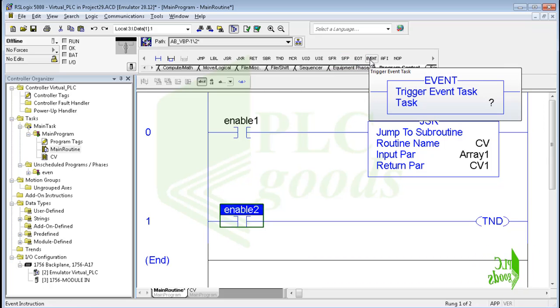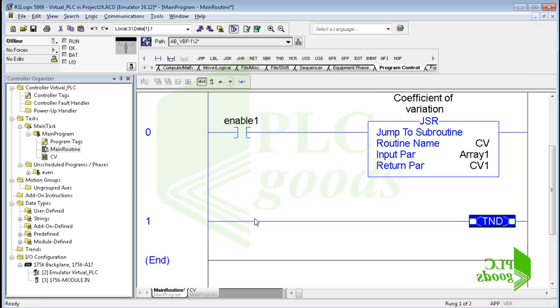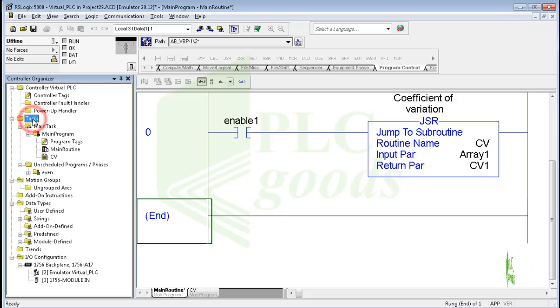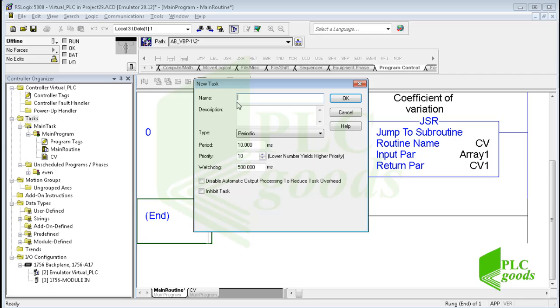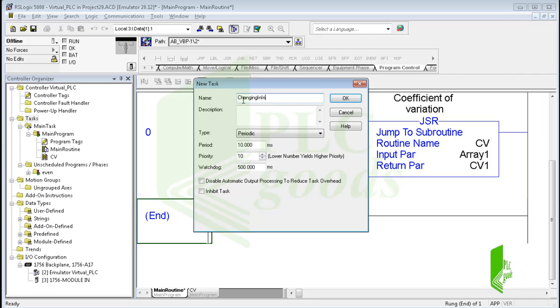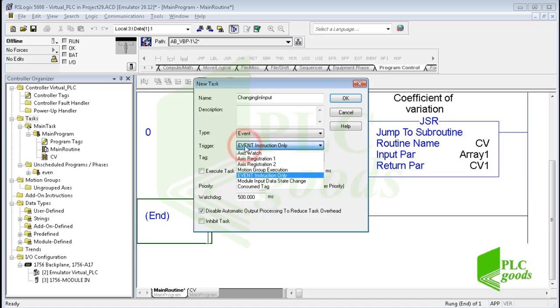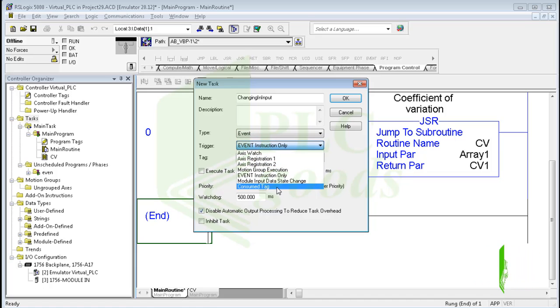Now let's see how the event instruction works. It works like the JSR instruction but calls another type of program. Let me create a new task — I write a name for the new task, and in the type field I select the event type. When the trigger conditions occur, the new task will be executed one time. I select the condition: module input data state change. For this choice, I must also determine a module tag.